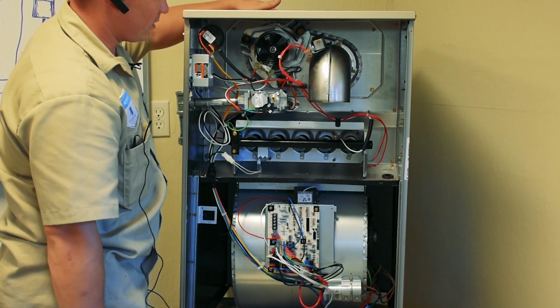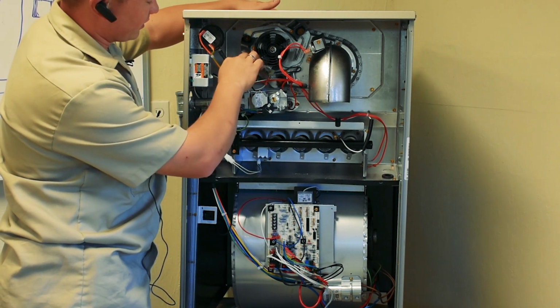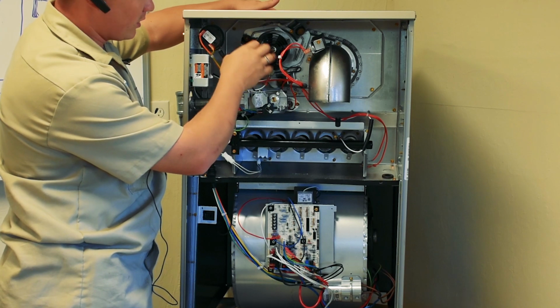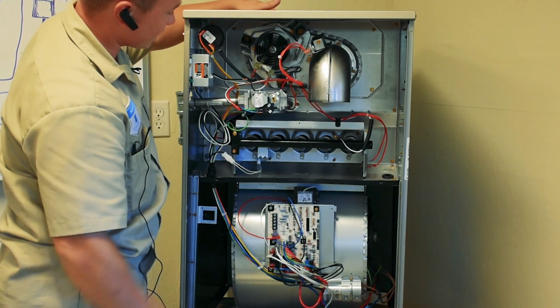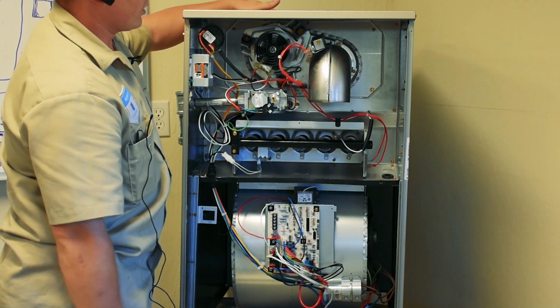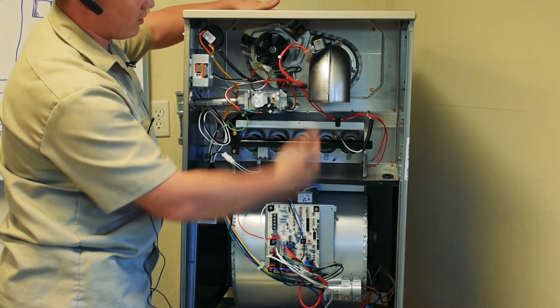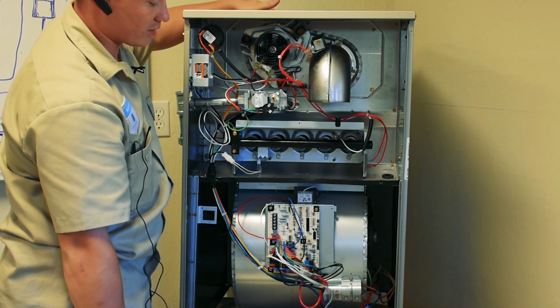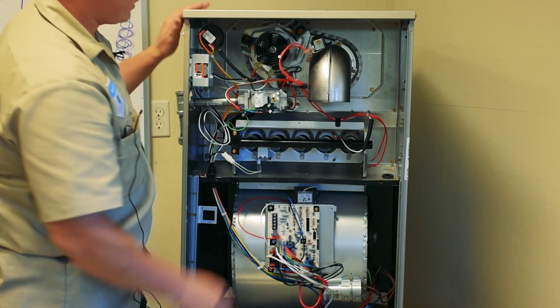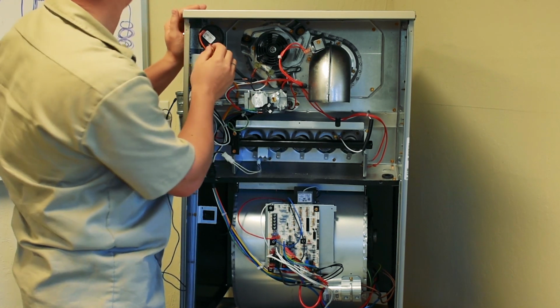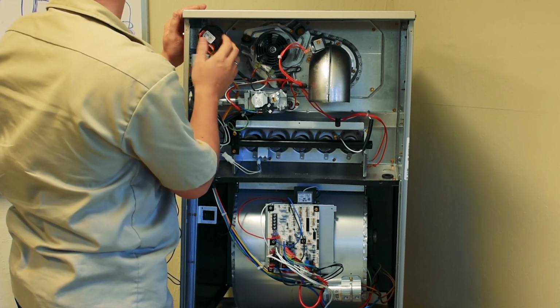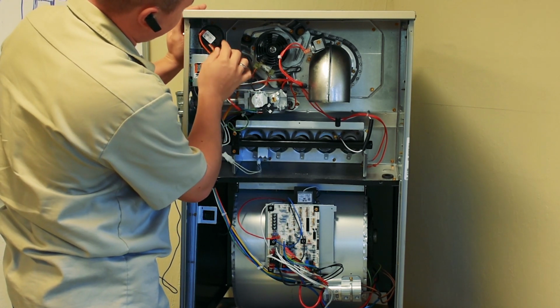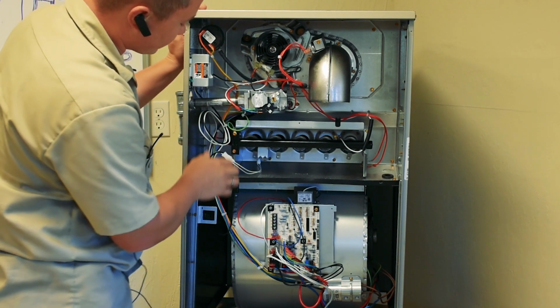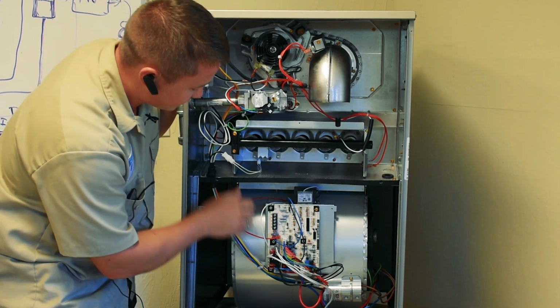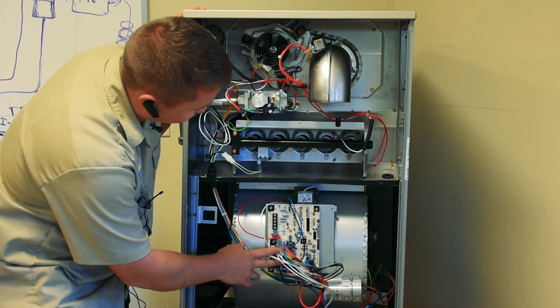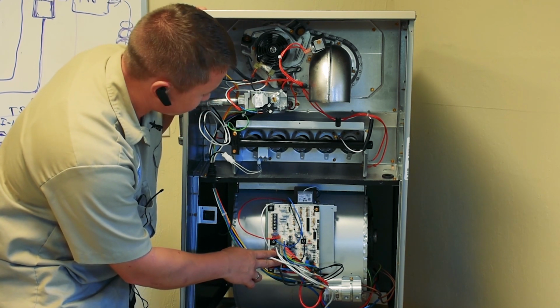In this case, it could be that the blower wheel motor is just not running, or something is wrong with the blower wheel inside this inducer motor. I mean the inducer housing, because it couldn't run out the carbon monoxide and carbon dioxide. Okay, when this pressure switch is actually closed, that's the third step: the signal that the pressure switch is closed is going to the control board. The control board will see that the pressure switch is closed.